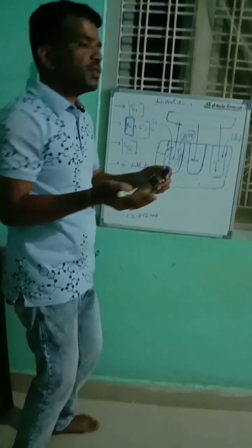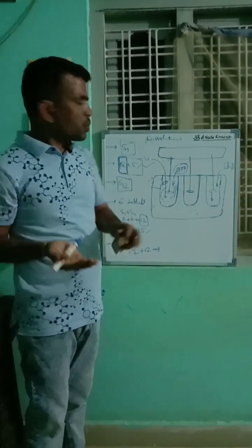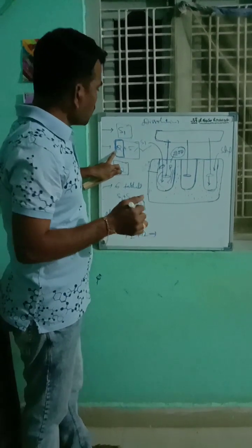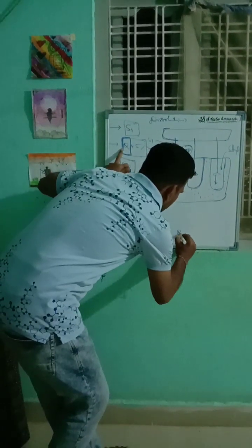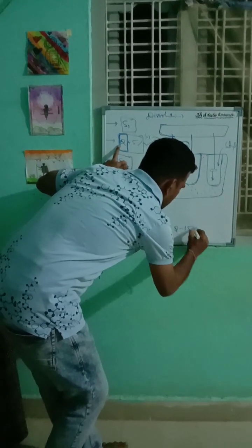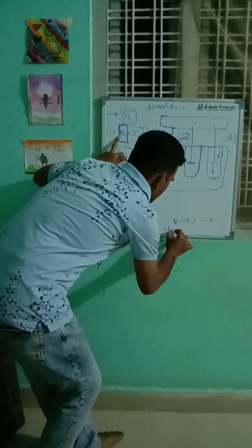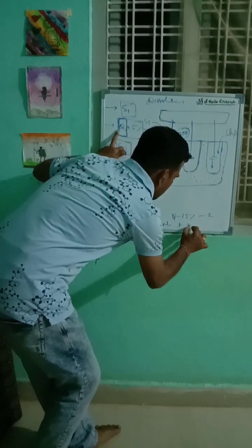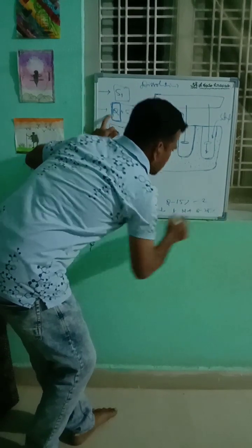The average of the 24 units should be greater than or equal to Q, and you can tolerate no more than 2 units below Q minus 15%, and no unit should be less than Q minus 25%.